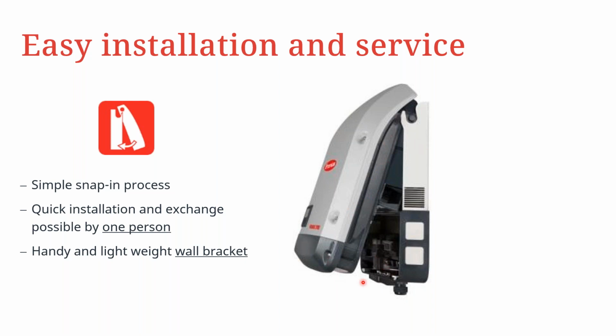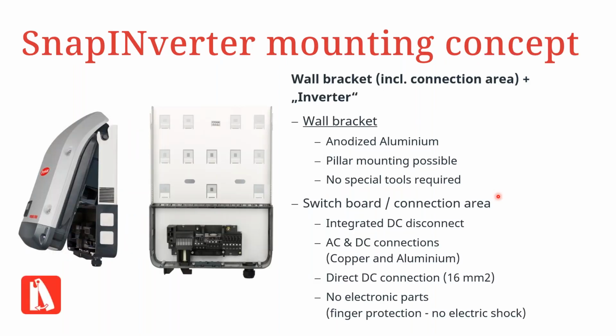The most important thing to note is that once the inverter is put into the mounting bracket, there are two screws at the bottom, one to the left and one to the right, that need to be tightened securely. The applicable torque is also printed on the inside of the Datcom cover. That ensures proper marrying of the inverter to the connection area for DC and AC power. That prevents damage that could occur due to sparking or overheating resulting from loose connections.